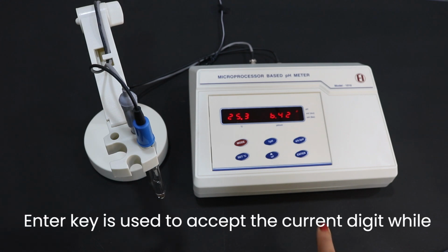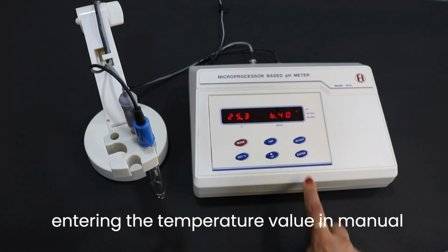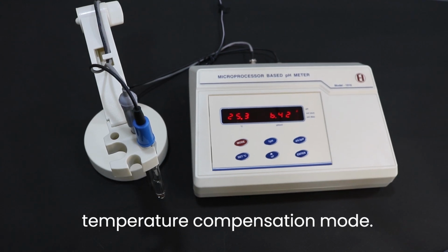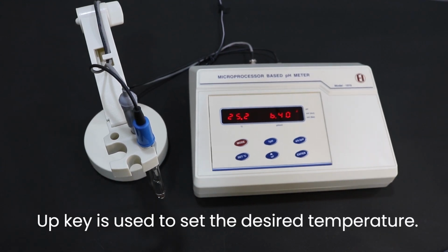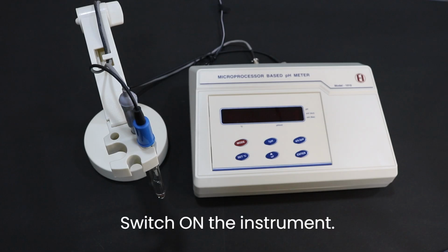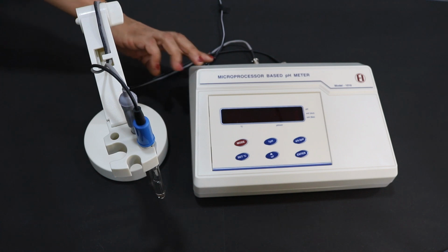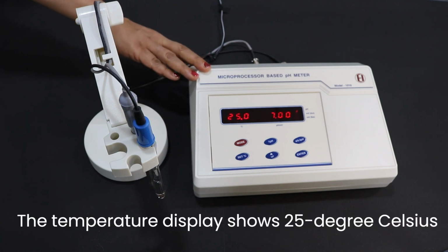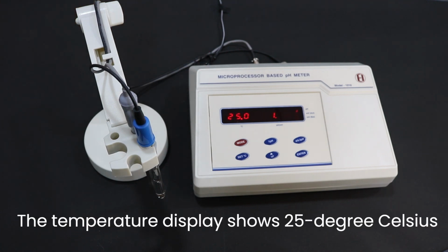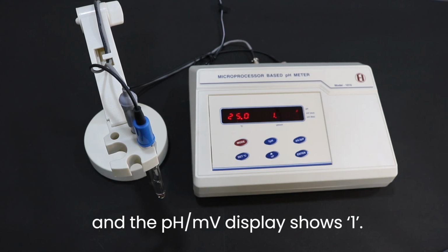Enter key is used to accept the current digit while entering the temperature value in manual temperature compensation mode. Up key is used to set the desired temperature. Switch on the instrument. The temperature display shows 25 degrees Celsius and the pH or MV display shows 1.